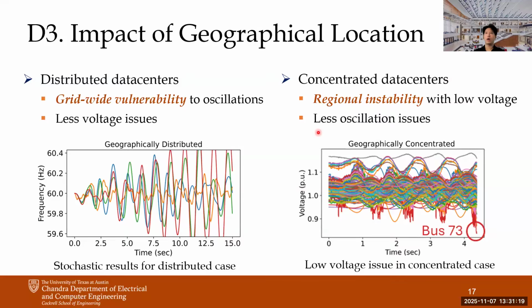So when we design the geographical locations of data centers, from the oscillation perspective, concentrated data centers would be more helpful for the grid compared to distributed data centers. But as you can see from this right figure, concentrated data centers are vulnerable to voltage stability issues. So when designing these locations, we need to consider these counterparts: the oscillation perspective and the voltage stability perspective.